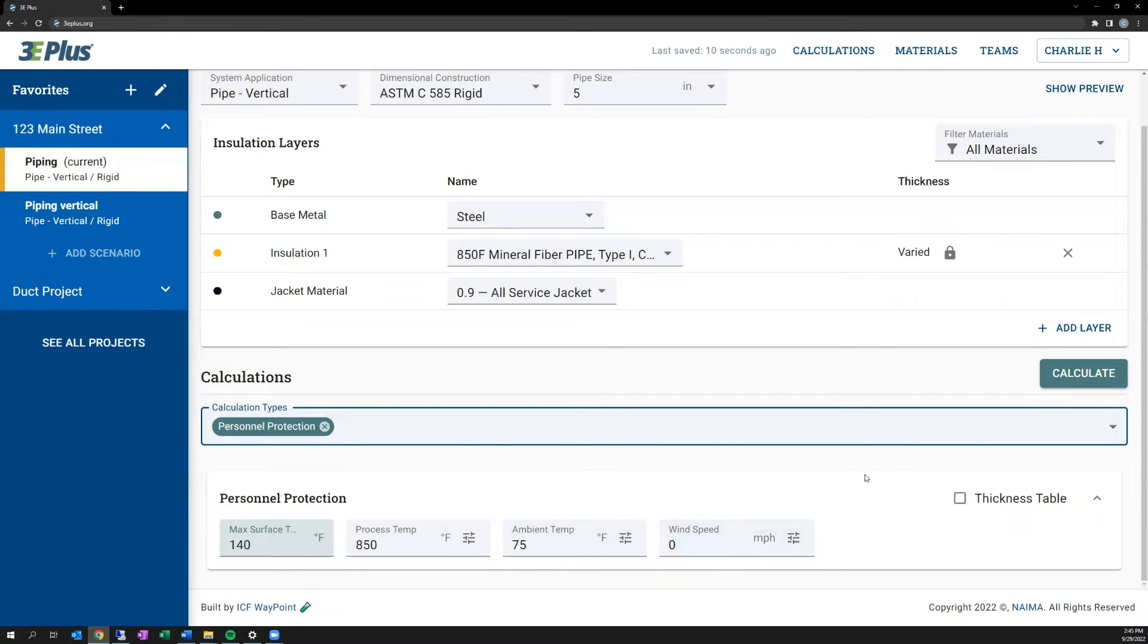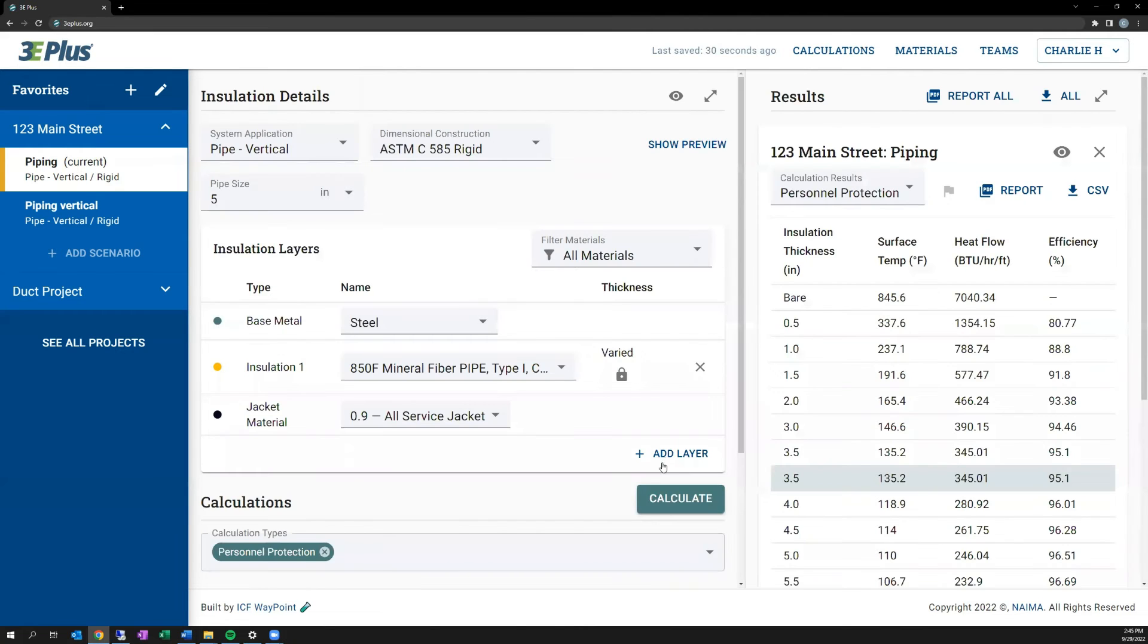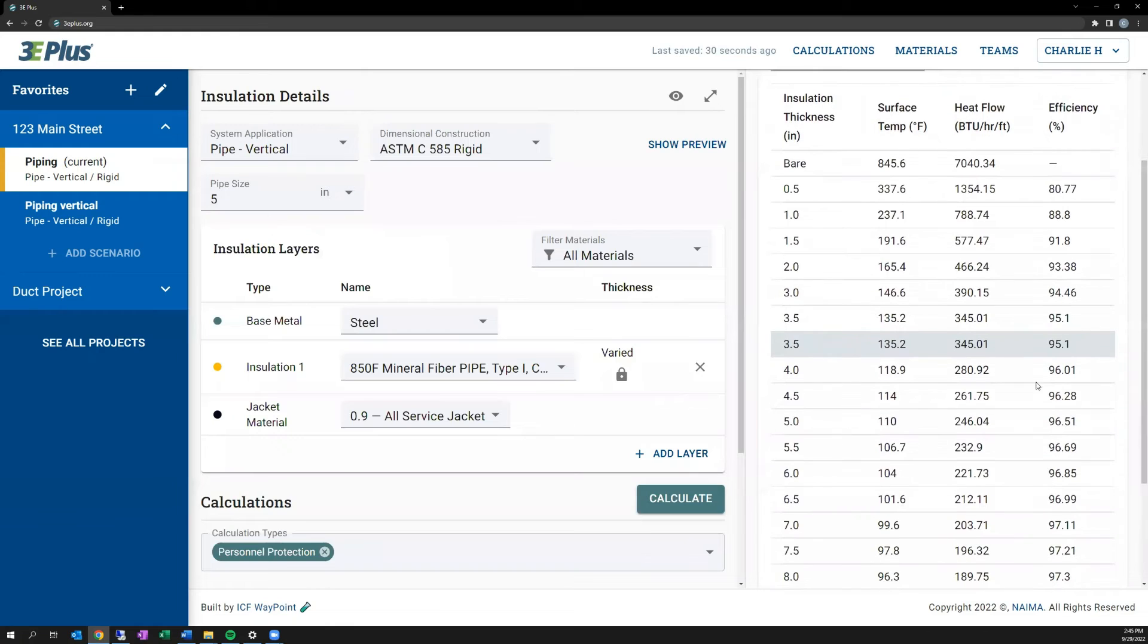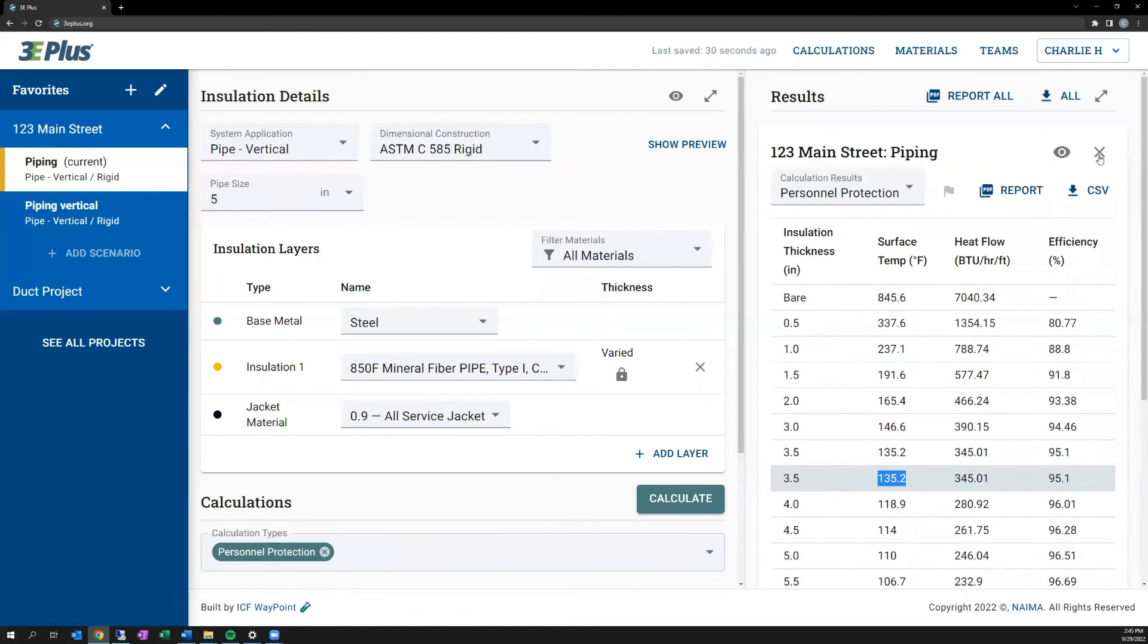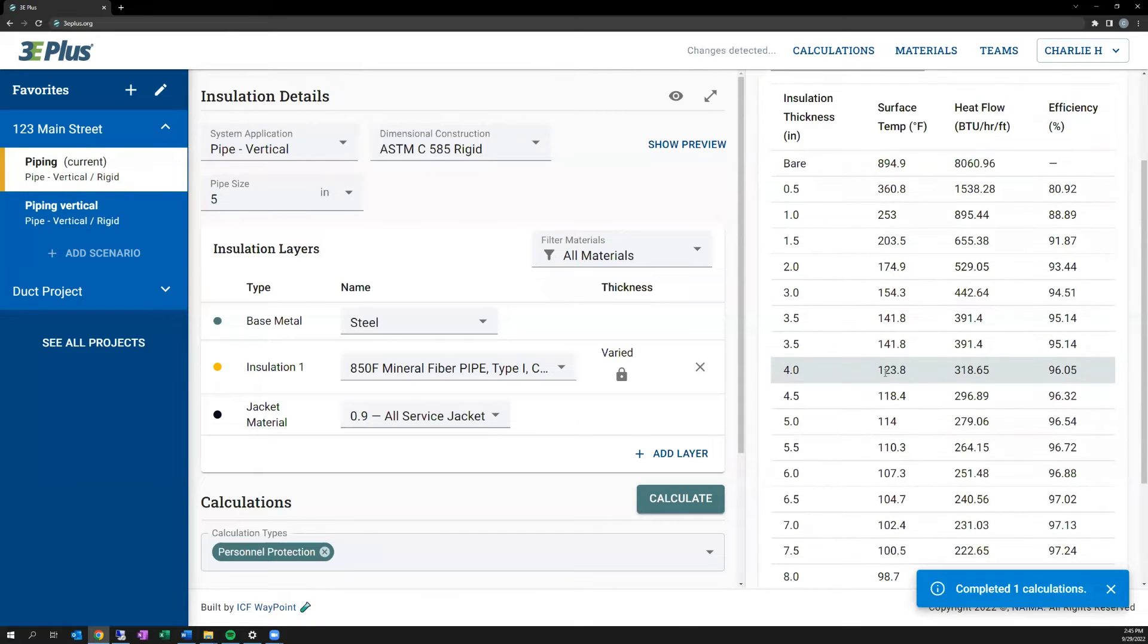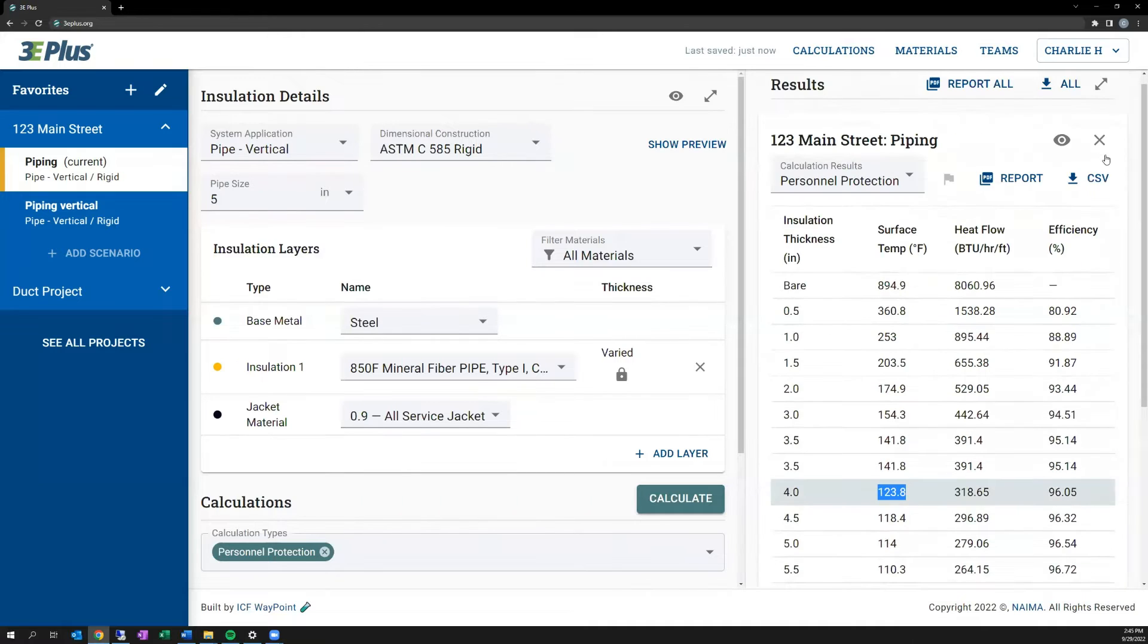After calculating, you'll see that one row is highlighted green, and that's the lowest level of insulation that satisfies the design goal of 140 degrees Fahrenheit. And you can see here, three inches, 146, three and a half is 135.2. Similarly, if I were to increase the process temperature, you could see that it will require more insulation to bring that temperature down. In this case, it moves it up to four inches.